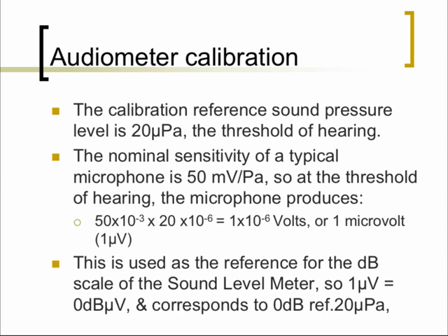The nominal sensitivity of any precision microphone is about 50 millivolts per pascal. If you were to use the threshold of hearing — 20 micropascals — in this equation, we can quickly determine that the sensitivity of a typical microphone is about 1 microvolt. So if it were to capture a sound right at threshold, the output of the microphone would be 1 microvolt, which is fed into the sound level meter.